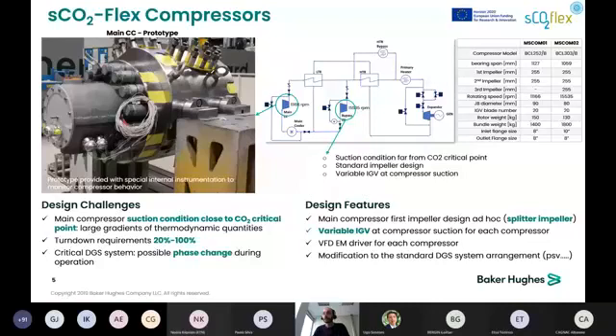But on the other hand, for these special applications we need a partial redesign of some machine components. For example, the first impeller of the main compressor has been redesigned in collaboration with the Politecnico di Milano in order to mitigate the sonic blockage effect triggered by the reduction of saturation margin available at the impeller intake. For the bypass compressor, as it is working far away from the critical point, this redesign has not been necessary.